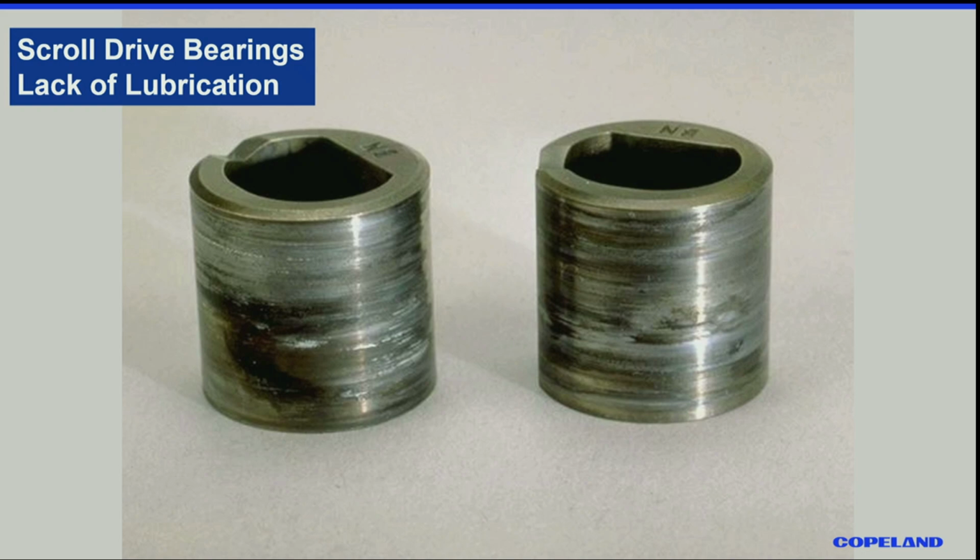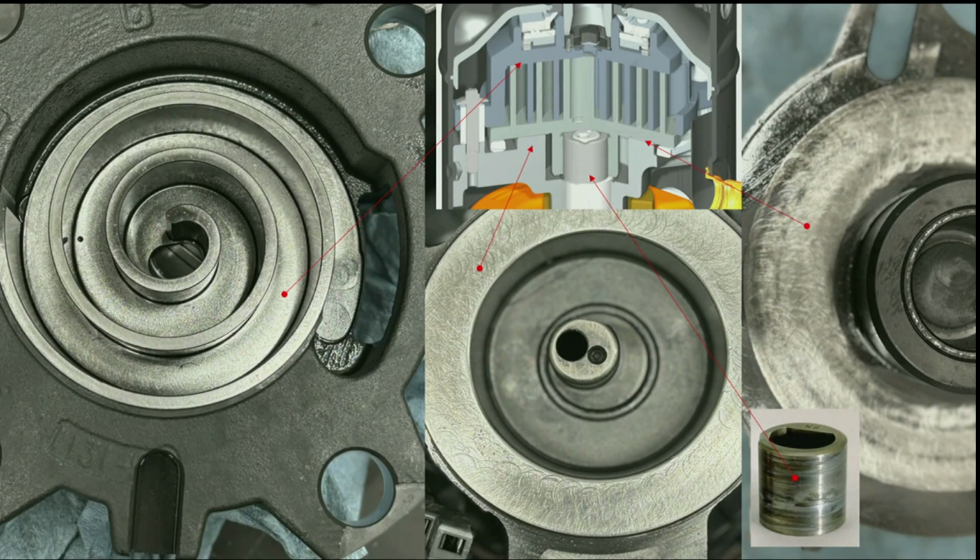And in extreme cases, well, this is actually the compressor that I'll be showing. This is a ZOD58 CO2 compressor. It had a lot of wear. You can see the little circular patterns here. That's the surface up in here. Down this thrust surface is where what we call the Oldham coupling comes in contact with this surface as well. So there's some wear in here. And of course, our drive bearing sits right here in the middle.